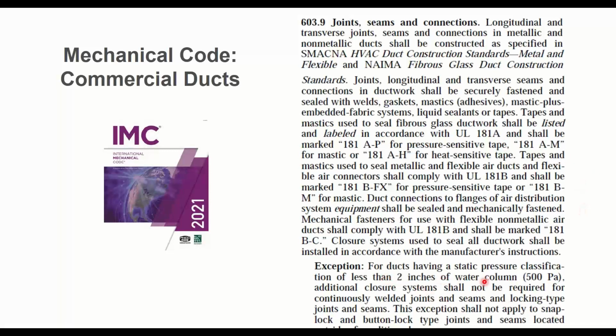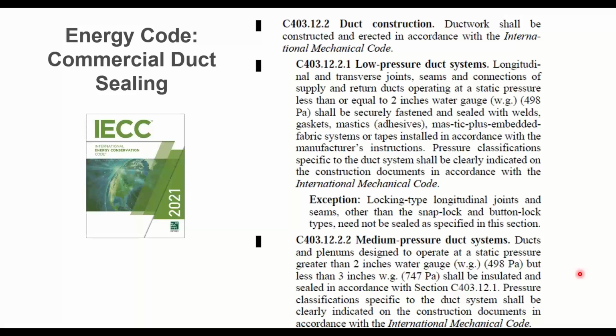Then down at the bottom here, when you get to ducts that have higher pressures, then you're going to get some more requirements that kick in. But that's pretty high pressure. The energy code, still continuing on with that. There's low, medium, and high pressure systems. Low pressure systems means less than 2 inches of static. And specifically, they're telling you you got to seal the longitudinal and transverse seams and connections. When you get up to medium pressure systems, that's 2 to 3 inches. And they're basically telling you you have to seal everything.